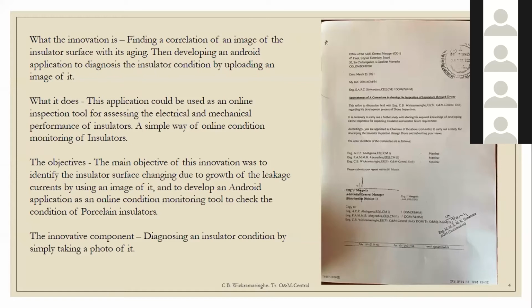And as we know, the world trend is now onto online condition monitoring tools, inventing online condition monitoring tools, because of the heavy loadings of the transmission lines and the number of insulators of a transmission line is very high. Because of that, offline condition monitoring of insulators is not feasible. Actually, we cannot take transmission line outages for months. Therefore, online condition monitoring is coming into the picture.